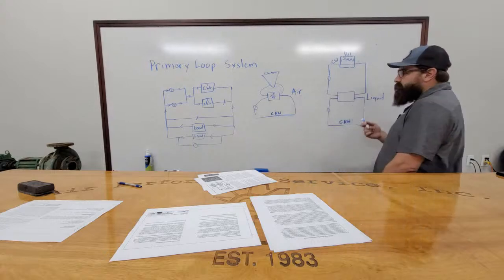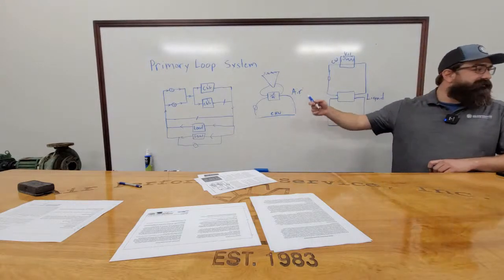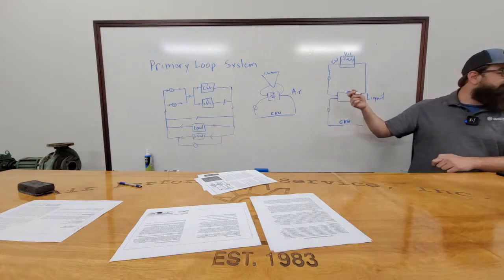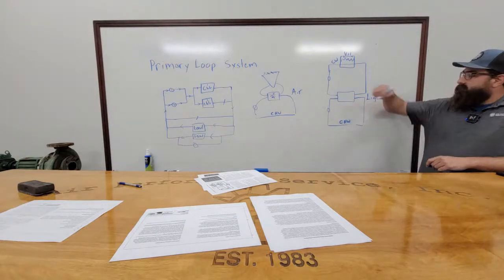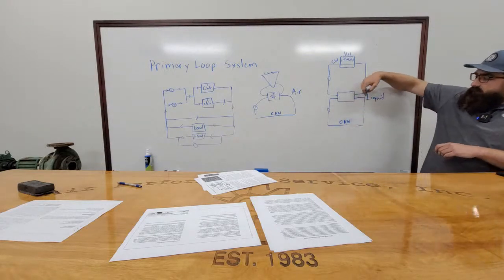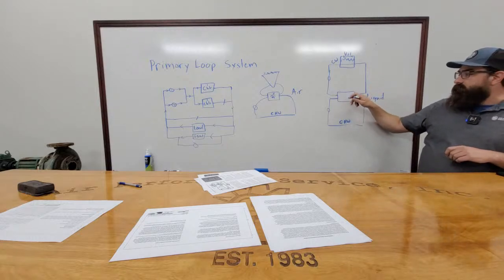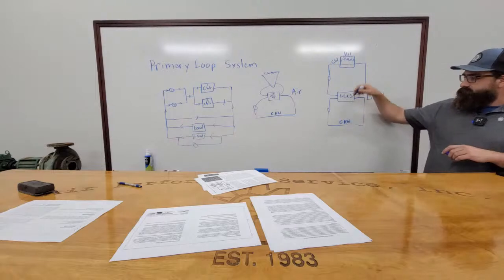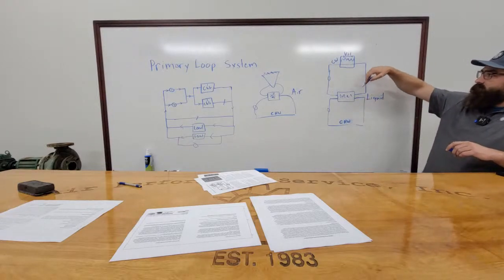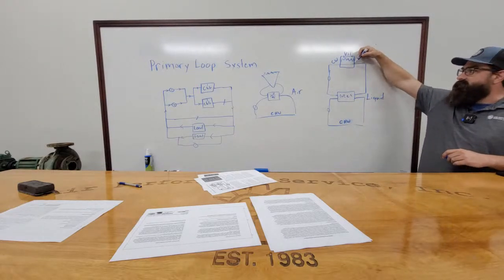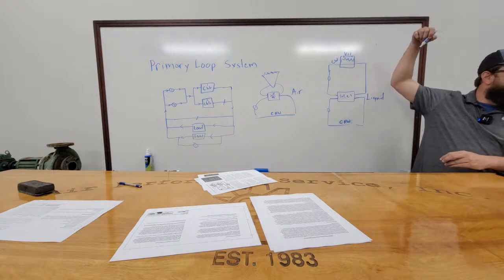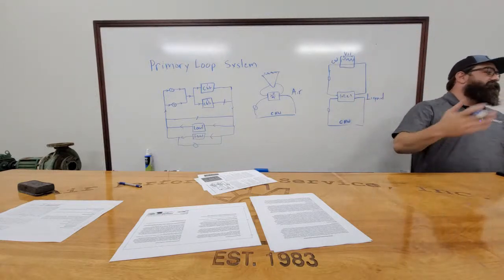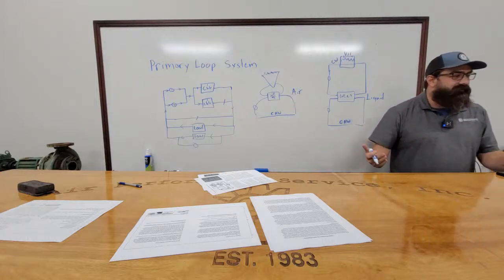On a liquid cooled, same basic principle as the air cooled, but you're using water to transfer your energy, your heat. In this case, the chill water loop goes through the evaporator. Condenser loop water comes through, pulls that heat out, brings it up to another heat exchanger, which then circulates water with air passing over it to draw the temperature out of that to completely reject it out of your system.